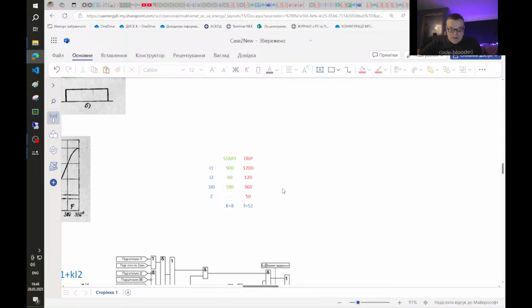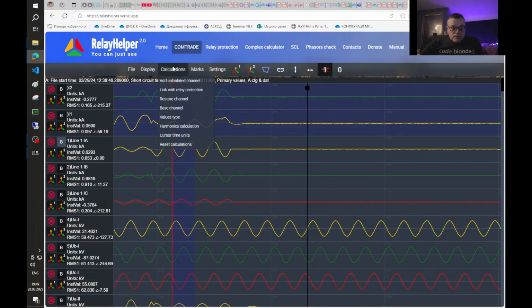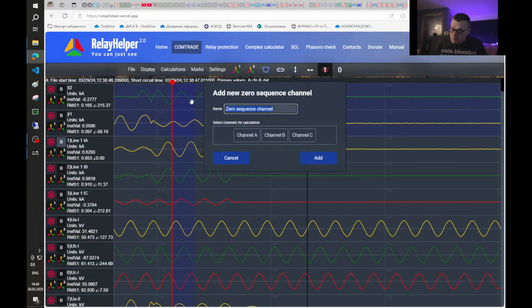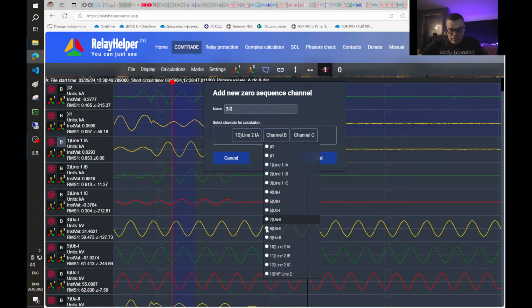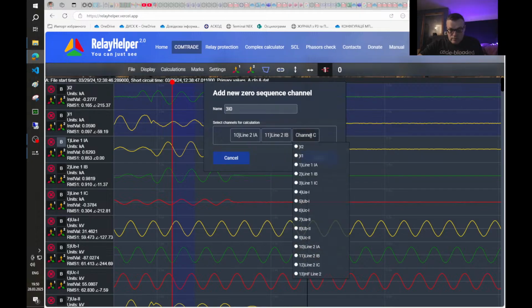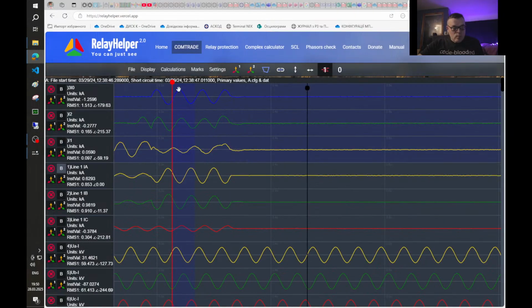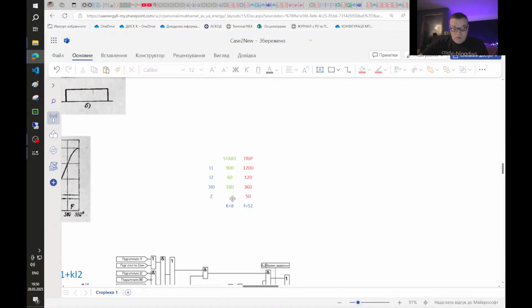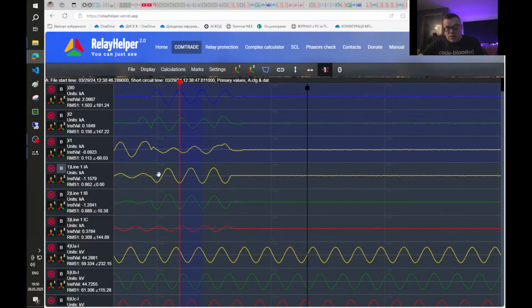So finally, let's check the zero sequence current. Something around 1,500 amperes. So these values also lead to start and trip signals. So let's check distance protection.